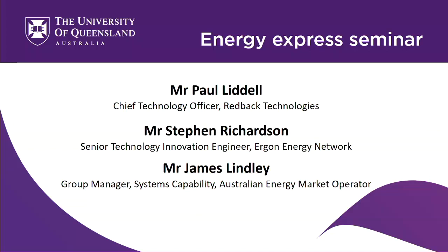Within Ergon, we've done some testing as well. One of the big things we've noticed is with three-phase faults - three-phase to ground, three-phase together - we get brilliant data. But as soon as you say 'I've got an unsymmetrical fault,' even some of the big players in the market, we can't get data out of them. They do not know how their inverters will perform with an unsymmetrical fault - a single phase to ground or a high impedance to ground, what happens? We get blank looks, and that's right up to their production engineers.